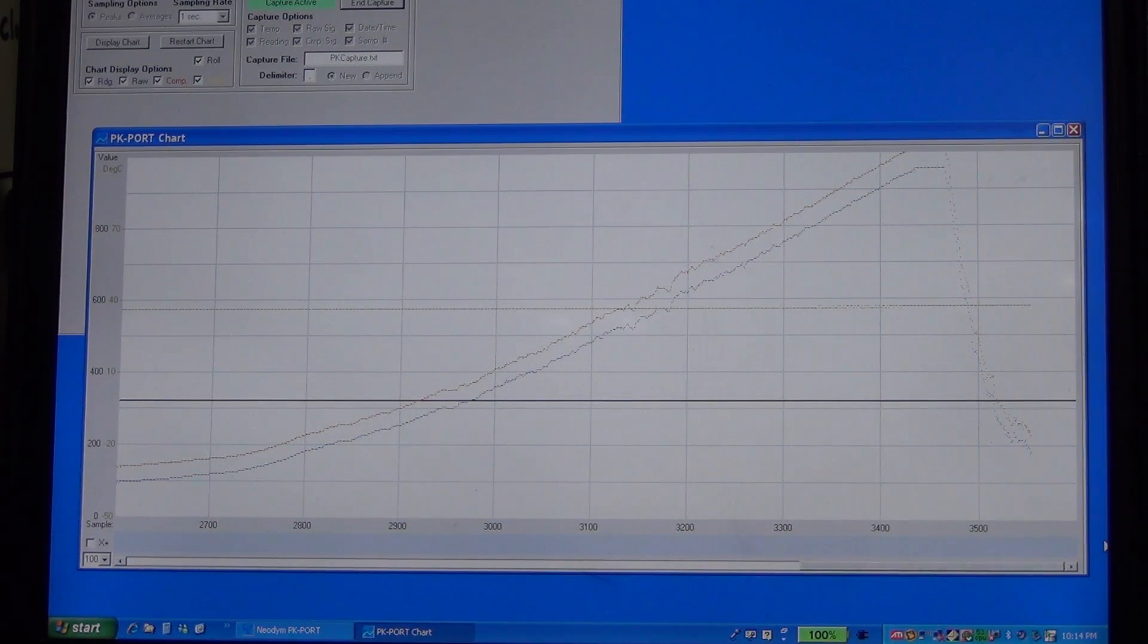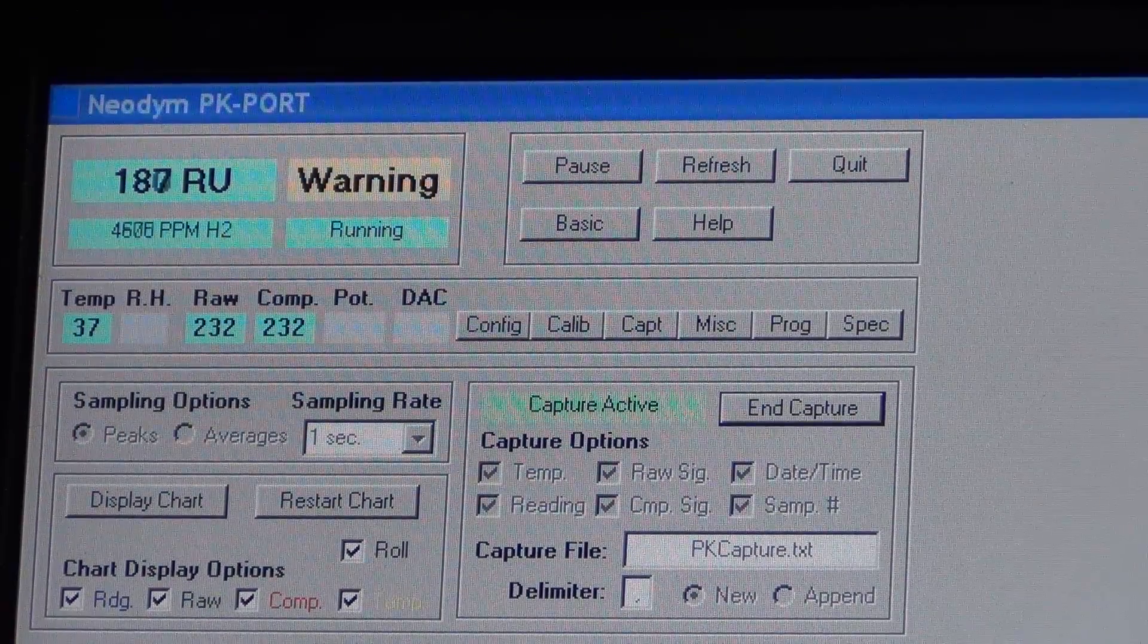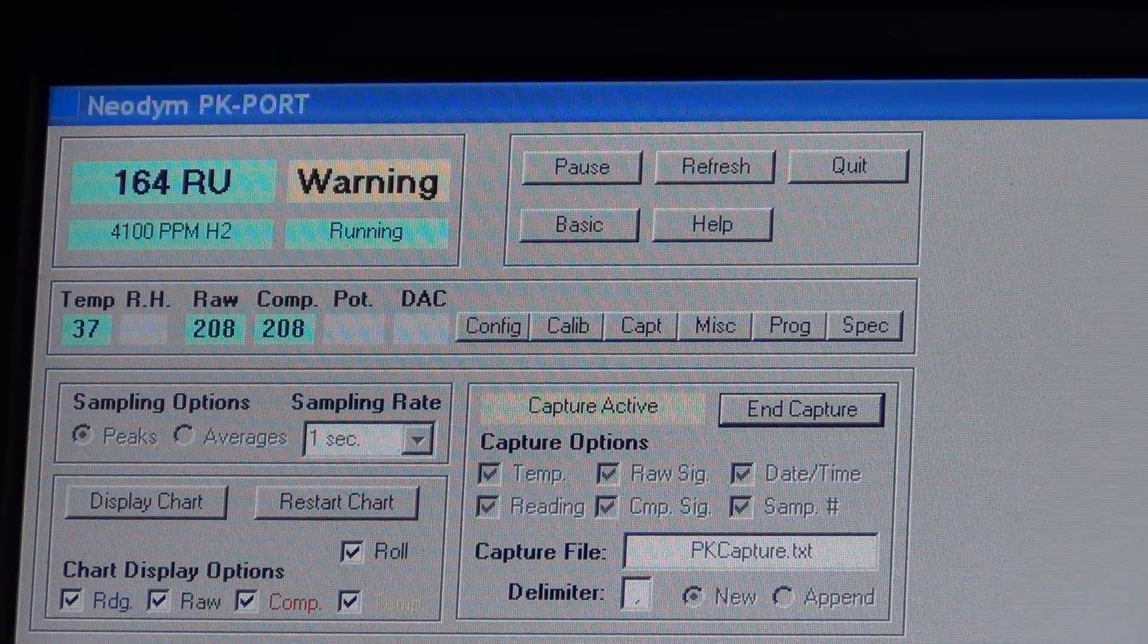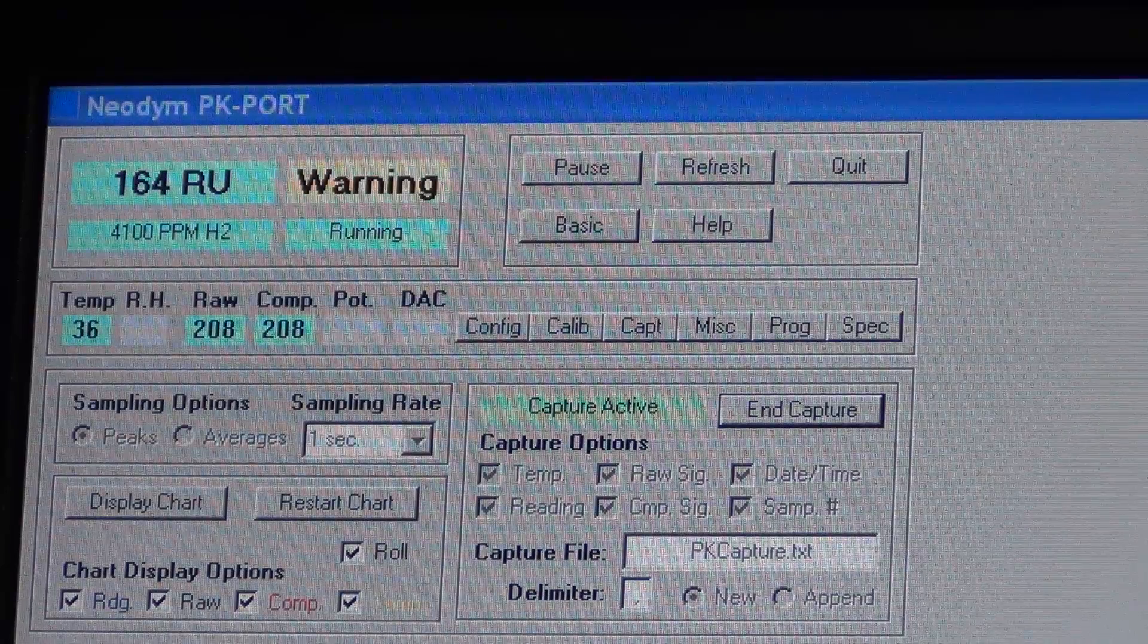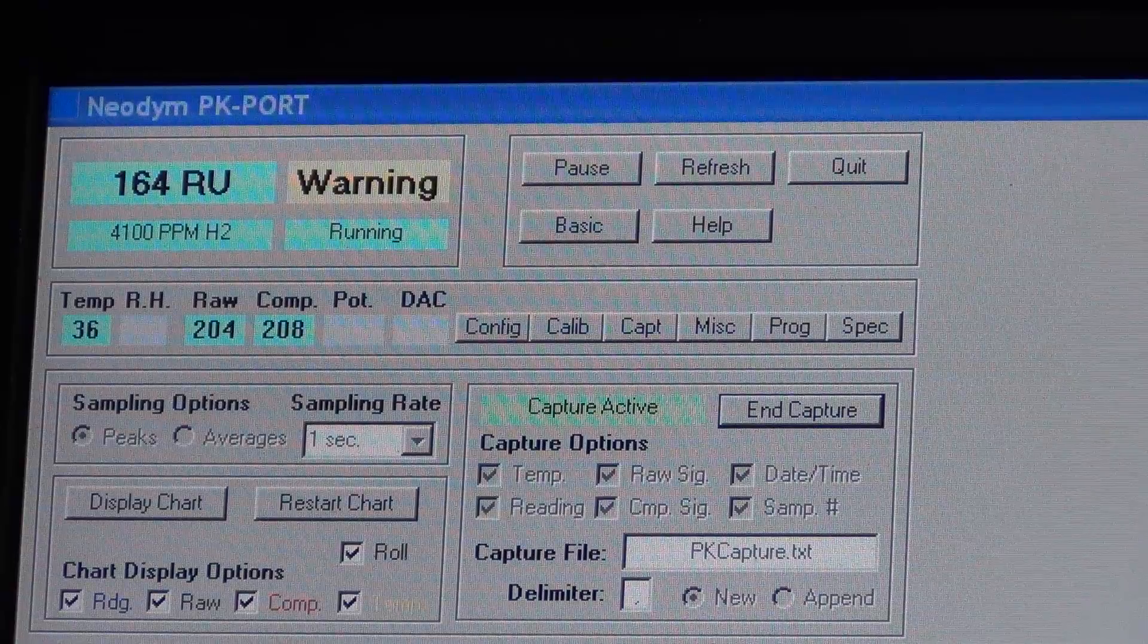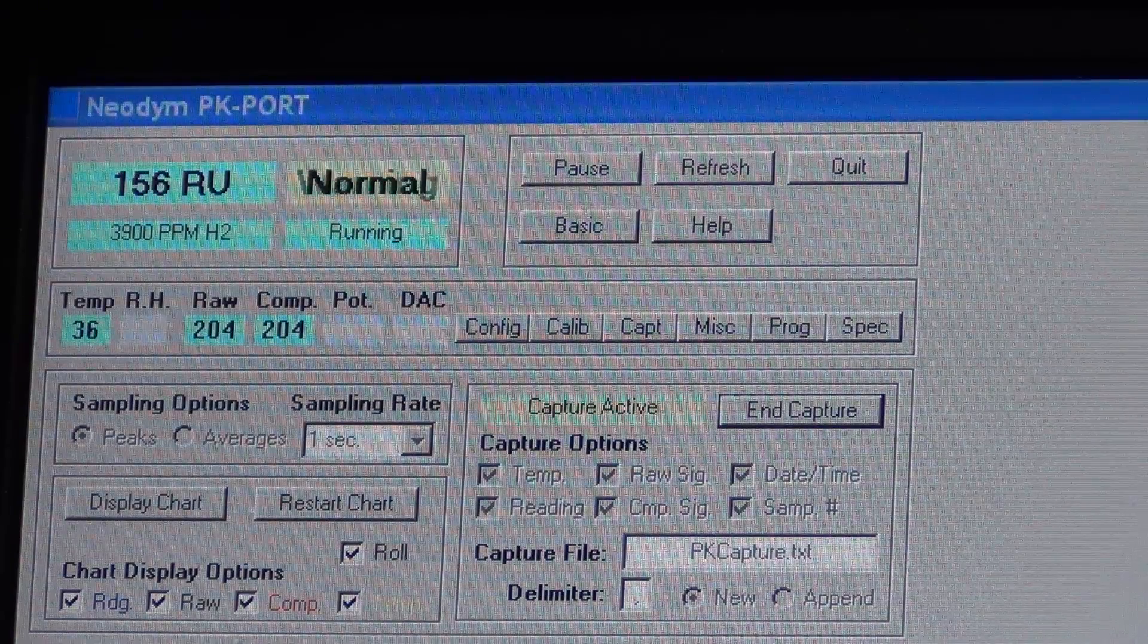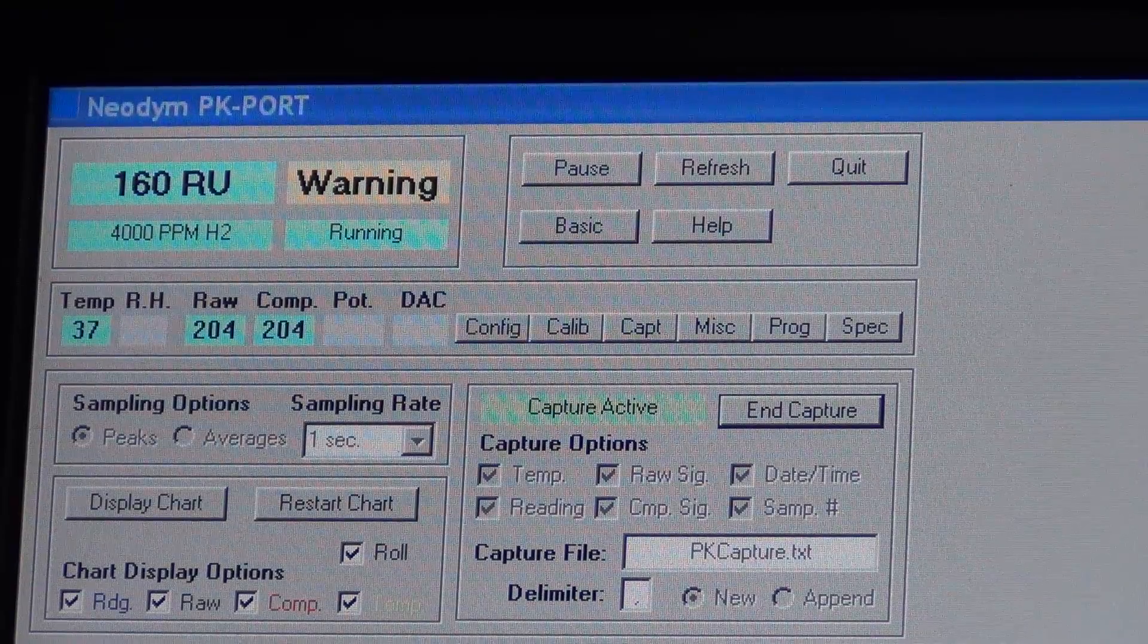And I will show you the ppm level here. There you are. And you can see the reading has really already dropped. It's at 4,100 and it's dropping really fast. So anyway, that gave us confidence that we do have a pretty good ventilation system here. And we also found that the fan, we have a fan here, but you really don't need a fan. The fan is more for thermal when the batteries, if they get a little bit too warm.